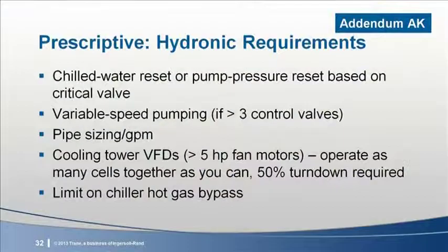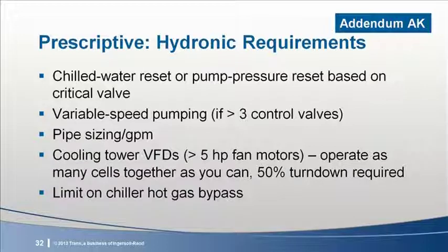The prescriptive section of the code tells us many things to expect our control system to coordinate. There is a new addition for 90.1 2013 for hydronic systems. This new twist is the requirement for either pump pressure reset, formerly the only compliance method, or chilled water reset. You will turn the set point up or down based on the critical valve being nearly wide open or until you reach the design limit of the system. The set point would either be pump differential pressure or temperature. Variable flow is required on hot and cold water systems once you have more than 3 control valves. This means you are required to have provisions to reduce flow to 25% of design flow or the equipment limits. In systems with pump motors larger than 5 horsepower, you are further required to use variable speed drives or equivalent performance on the pump motor.